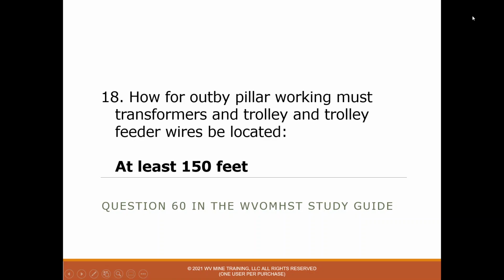18, how far out by pillar workings must transformers and trolley feeder wires be located? And the answer to that is at least 150 feet. So it has to be back much further from pillar workings. I've worked pillaring a little bit, and you really have to stay on top of this, because as you're moving back, you can get too close to your power center, and it has to be at least 150 feet out by the pillar workings.